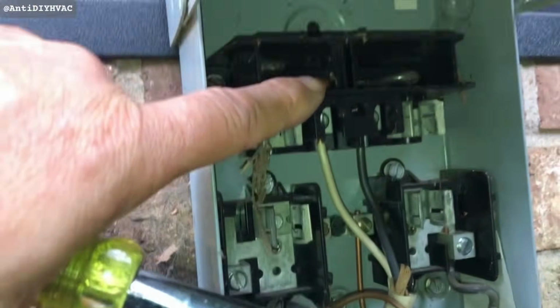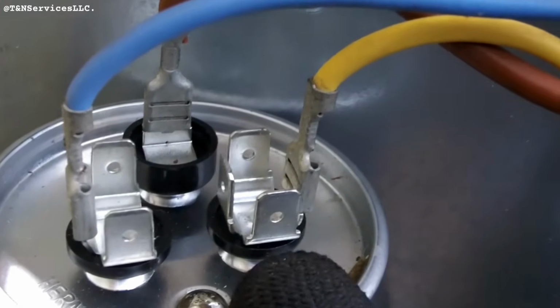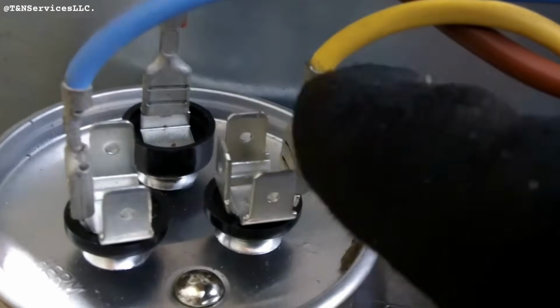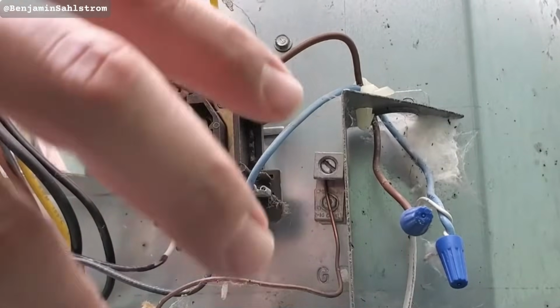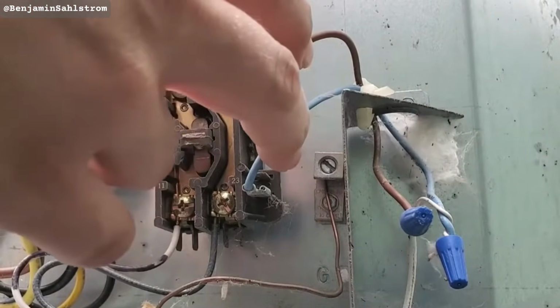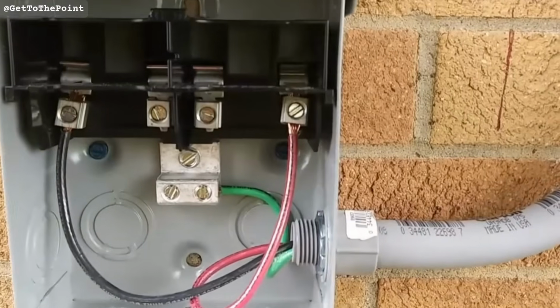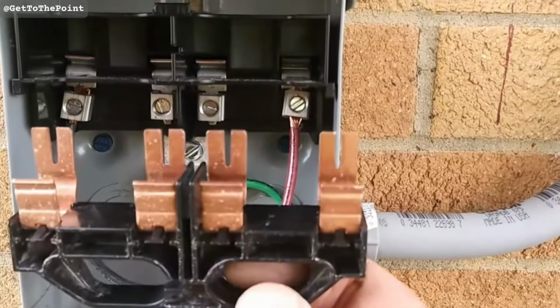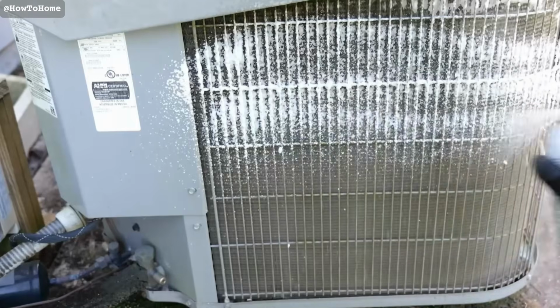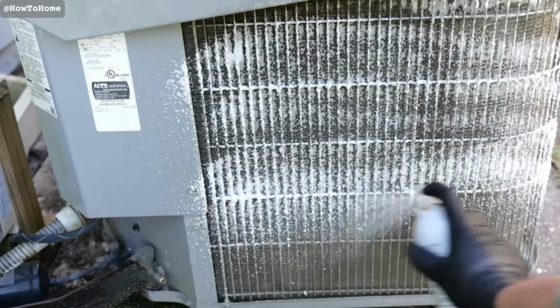I call. Cheap electrical components and visual checks, reversible. Pull a wire, label it with the masking tape, swap a part, test it. If it doesn't work, put the old one back. That's where I do my own work. And the single measurement I take twice a year that tells me more than every other check combined: the temperature split across the indoor evaporator coil.